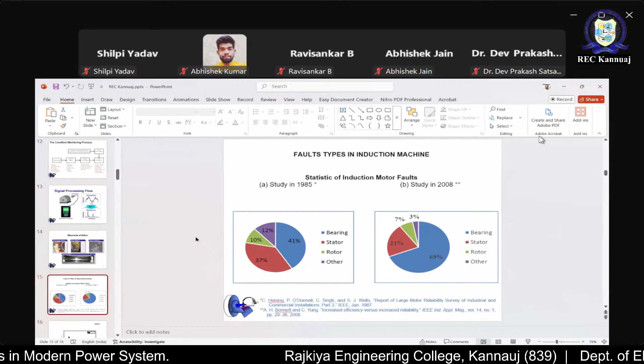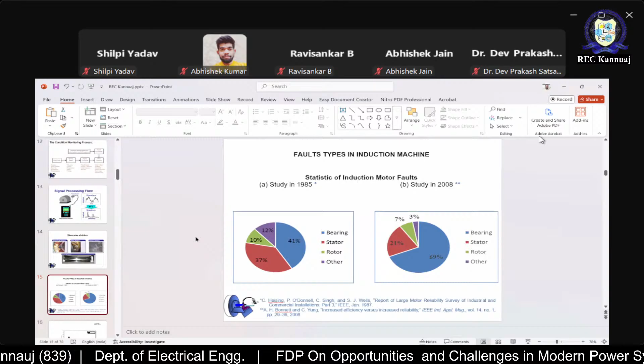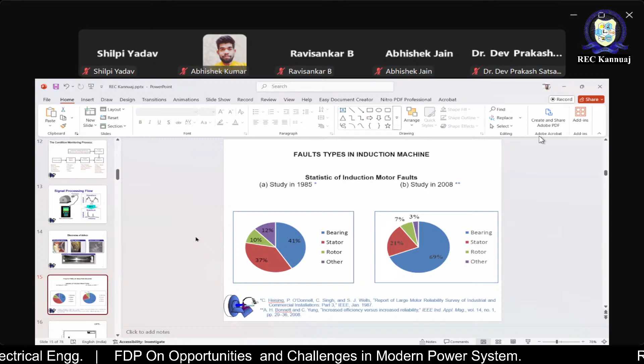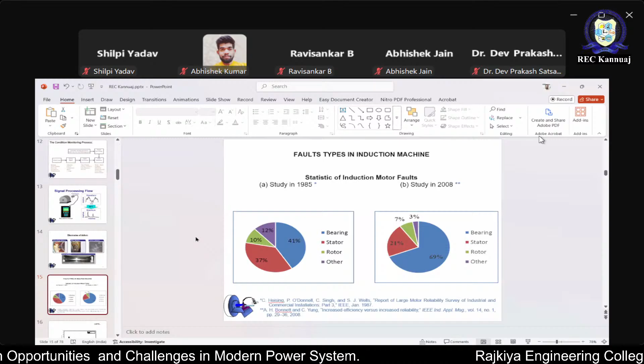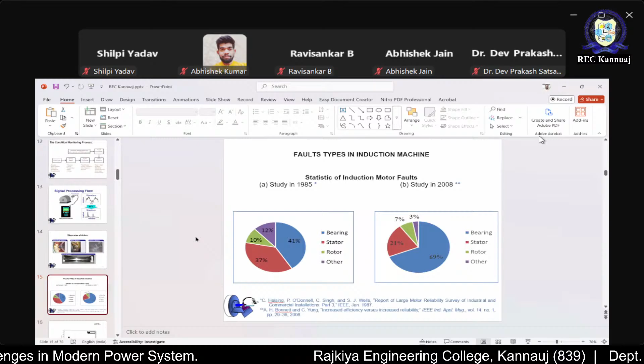But in the 2008 study, faults in bearings increased from 41% to 69%, and stator faults reduced from 37% to 21%. This information says that more focus is required for analysis of bearings, because of their continuous rotation, there is more chance of fault occurring in the bearing. So today's presentation will focus basically on the bearing part, faults, and how we will detect faults in the bearing.